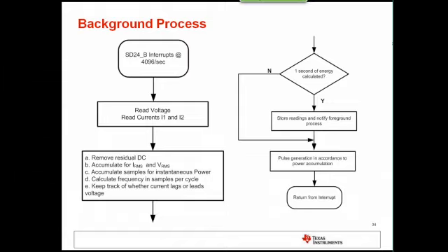This flow diagram shows the background process. You have an interrupt at a rate of 4096 hertz. Once you have the interrupt, you read the voltage and the currents, remove the DC using a DC filter, and accumulate the square of the current and also the square of the voltage. You also multiply the voltage and current together to get the instantaneous power, and you accumulate that. Whenever there is a zero crossing, you update the calculation for frequency, and based off of whether current is lagging or leading at a voltage zero crossing, you update information on whether a load is inductive or capacitive.